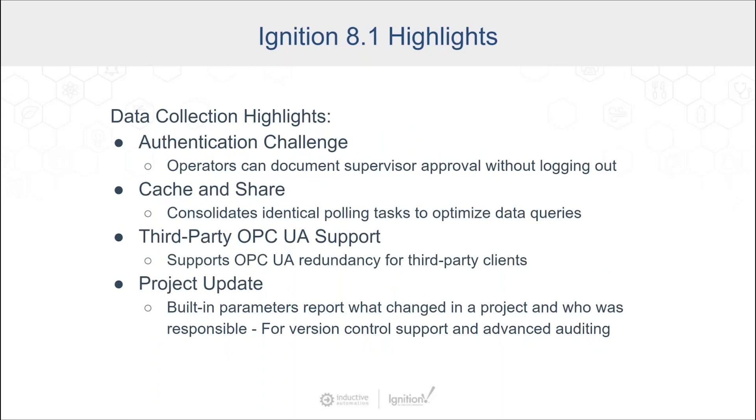The authentication challenge is nice for things like 21 CFR Part 11 or other things where you have to have some sort of validated actions. Somebody might need a supervisor to log in or at least put in their credentials to verify an action before you're able to write to a tag or make a change to a running system.